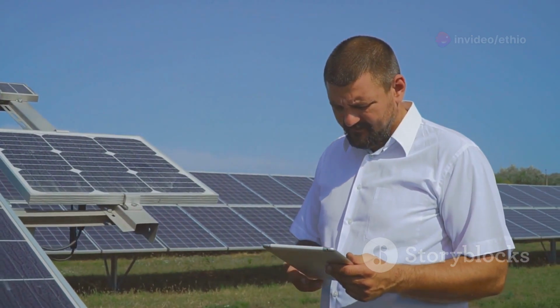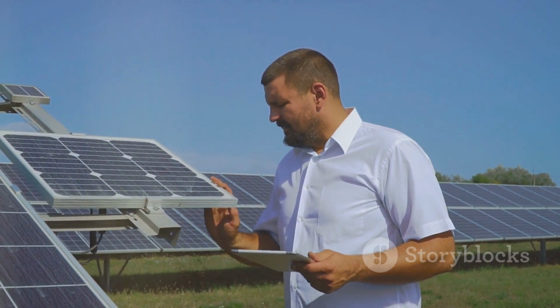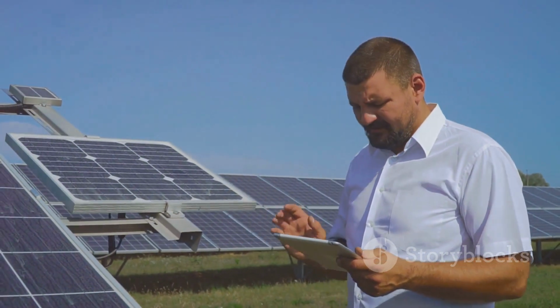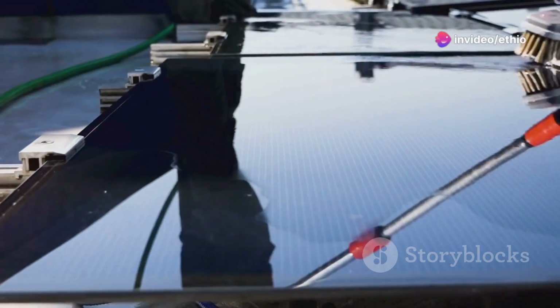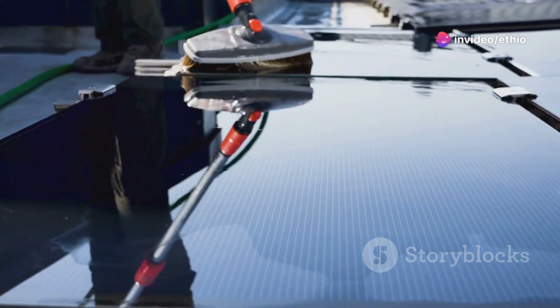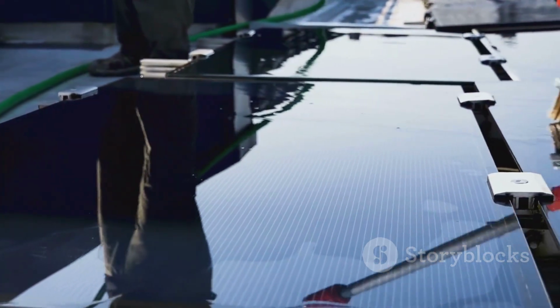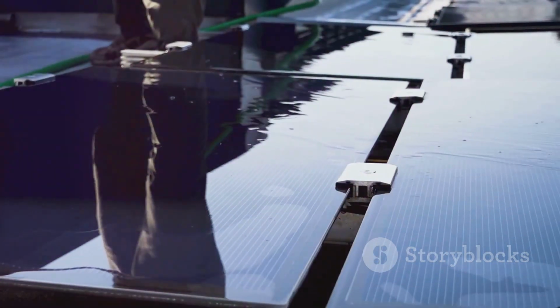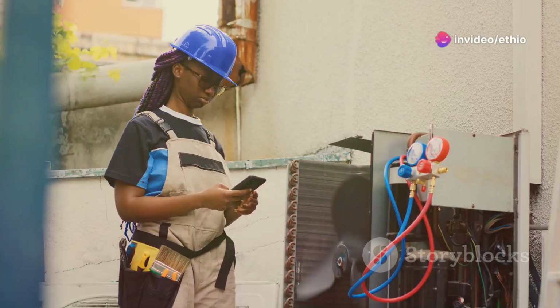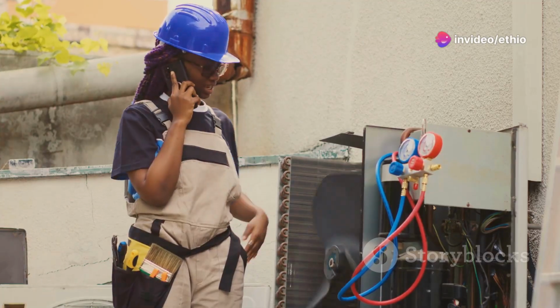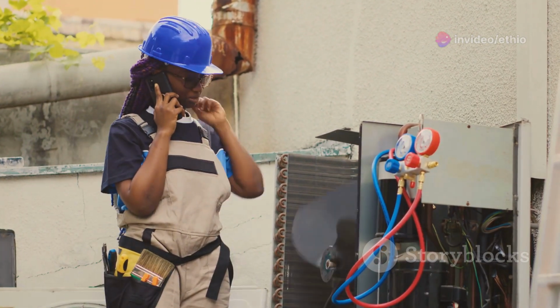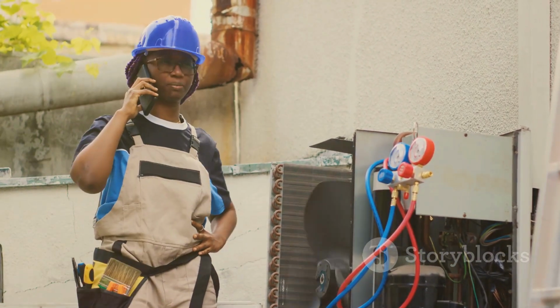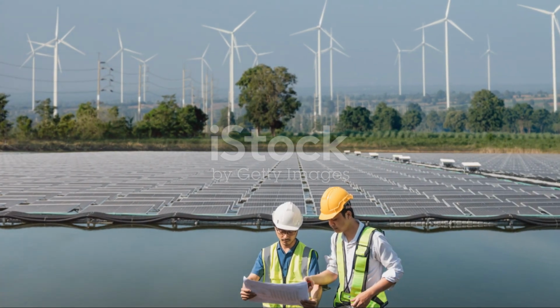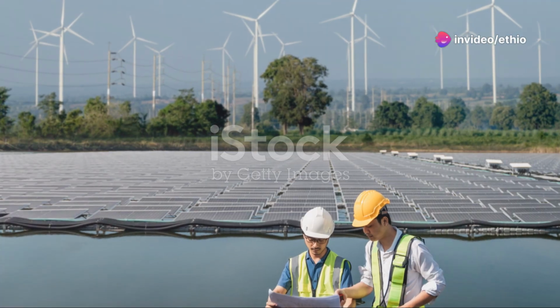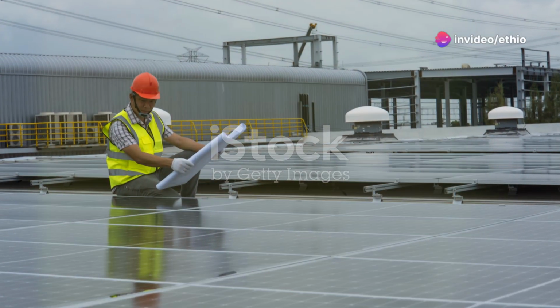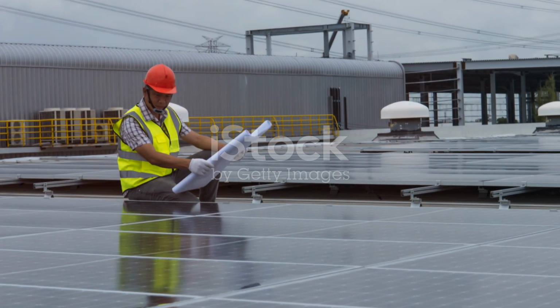For isolation faults, carefully inspect all cables for visible damage, fraying, or signs of water leaks, as these can cause dangerous faults. Moisture is a common culprit for many inverter errors. If you spot any water or condensation, dry the area thoroughly and address the source of the leak immediately to prevent further issues. If you've tried all these basic checks and the error still won't clear, don't hesitate to call your solar installer or the inverter manufacturer's support line for help. The experts can guide you through more advanced troubleshooting steps or arrange for a professional repair if needed, ensuring your solar system gets back to working safely and efficiently.